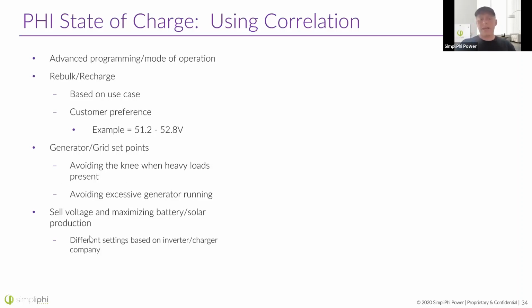Another question we often get is, as far as sell voltage, where should I set the sell voltage for my system? Well, it depends. Do you want to keep your battery more full, or do you want to sell as much power as possible? So often we see customers at 53.2 on their sell voltage. That's keeping the battery quite full and might reduce the amount of power you sell slightly. Whereas at 52.8 or 52.4, that battery's trying to pull in as much power as it can and push it back out to the grid. So it's really just based on your preferences.